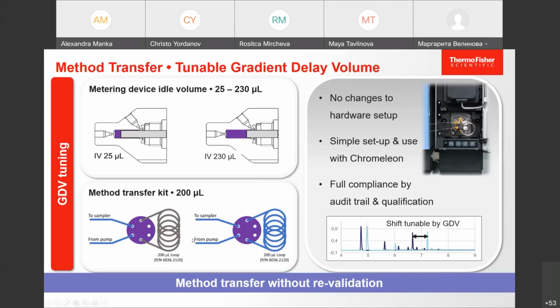And if that is not enough, you can also add the method transfer kit, which has a 200 microliter loop and a valve. This is how it looks in reality. You can switch this loop in and out of the flow. So we have 200 microliter added if you need them, or if you don't need them, you leave them out of your flow. It's really simple to set up and use in Chromeleon, and it's fully compliant because once it's installed, you just switch it in or out, you see it in the audit trail, and it's qualified with the system. And this is how you can shift your chromatograms with this gradient delay volume.